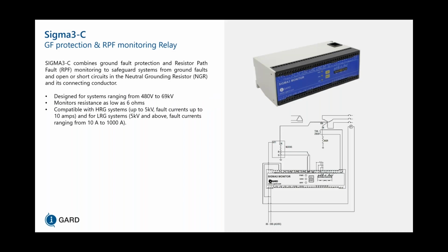Now let's take a look at resistor monitoring. Now, at I-Gard, we have our Sigma 3C ground fault protection and resistor path fault monitoring relay. The reason why we chose to go with resistor path fault is because we're monitoring the entire path between the XO point to ground, not just the NGR itself. So that includes the wire, the resistor, as well as the ground connection. So the Sigma 3C combines ground fault protection and resistor path fault monitoring to safeguard systems from ground faults and open or short circuits in the neutral grounding resistor, or NGR, and its connecting conductor.